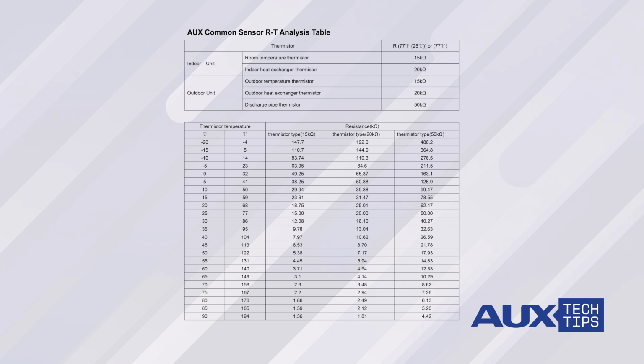If it is significantly off or shows no resistance or an open circuit, the thermistor is faulty and could cause your error code. It is time to replace your thermistor. For extra accuracy, it is always good to test at a different temperature. To do this, place the thermistor in warm water around 100 Fahrenheit and measure the resistance. Use the sensor chart to verify the expected value, which should be lower than the room temperature. Testing thermistors on the AUX mini-split is easy using error codes and the thermistor chart.